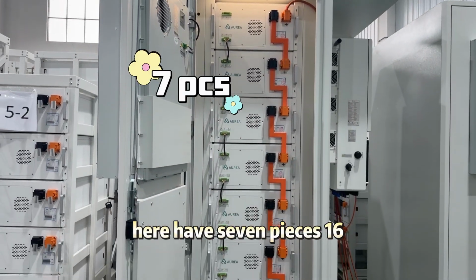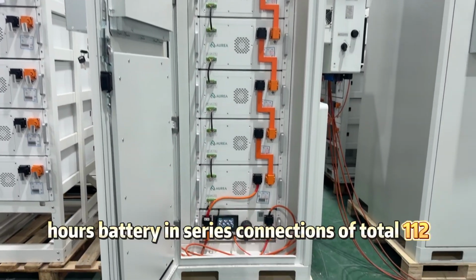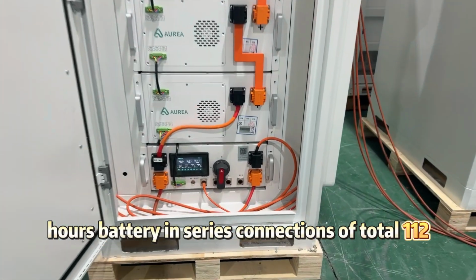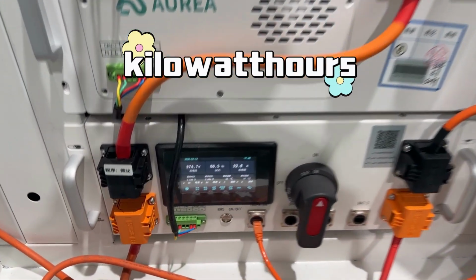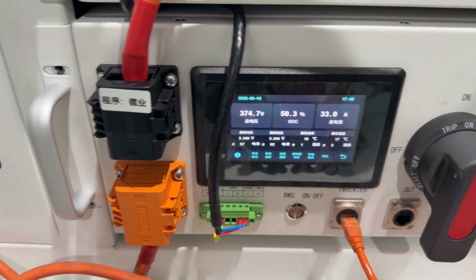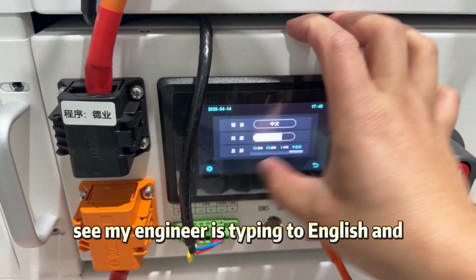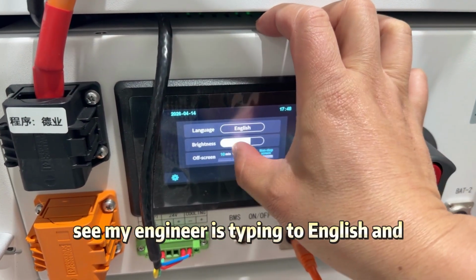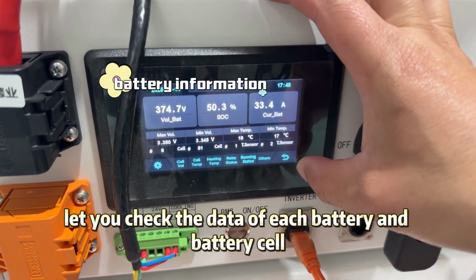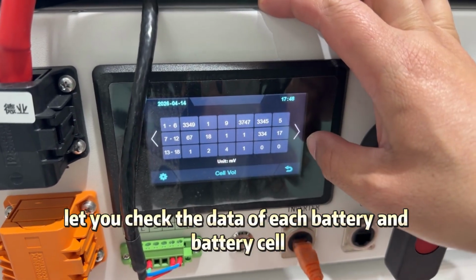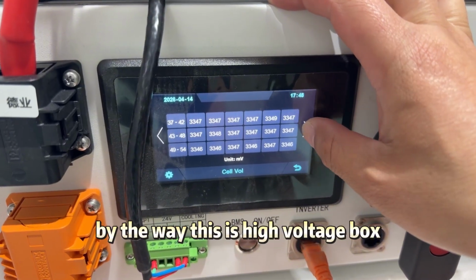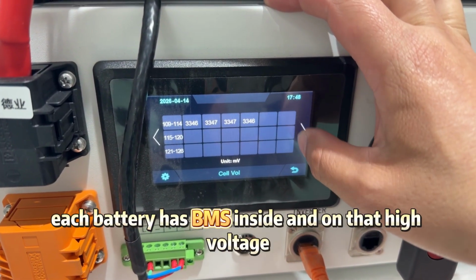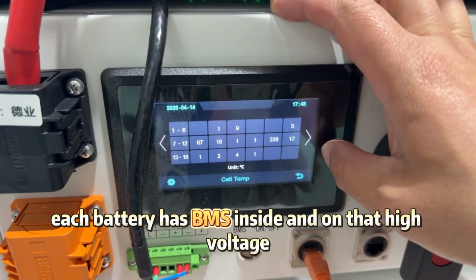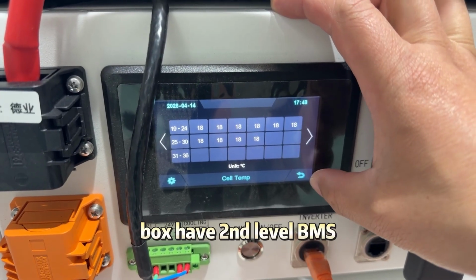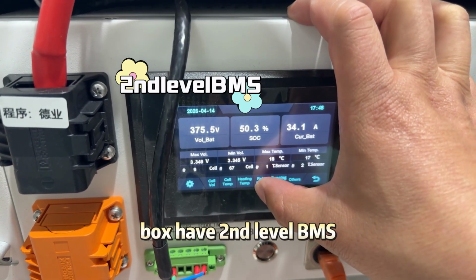Here I have 7 pieces of 16 kilowatt hour batteries in series connection, totaling 112 kilowatt hours. My engineer is typing in English so you can check the data of each battery and battery cell. By the way, this is the high voltage box. Each battery has a BMS inside, and the high voltage box has a second level BMS.